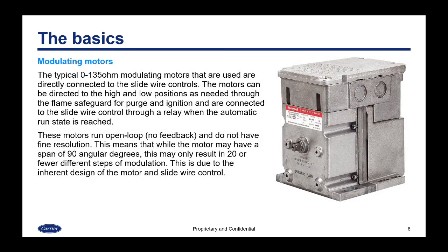The typical 0 to 135 ohm modulating motor that is used can be directly connected to the slide wire controls. The motors can be directed to the high and low positions as needed through the flame safeguard to purge and for ignition, and they are connected to the slide wire control through a relay when automatic run status is reached, and that's when modulation will occur. These motors run open loop, which means there's no feedback. The flame safeguard doesn't know where they are, and they do not have fine resolution. This means that while a motor may have a span of 90 angular degrees, this may only result in 20 or fewer different steps of modulation. And this is due to the inherent design of both the motor and the slide wire control itself.